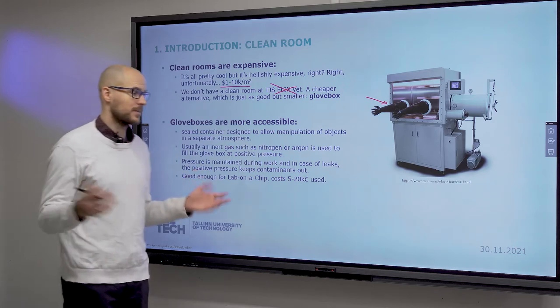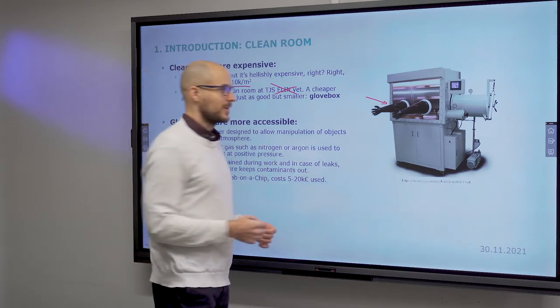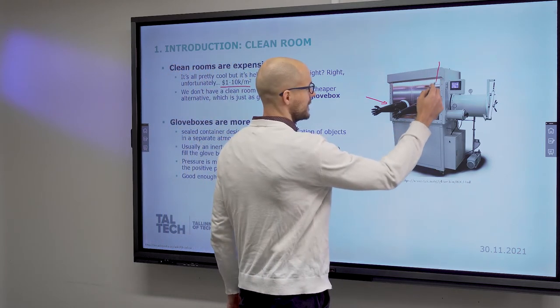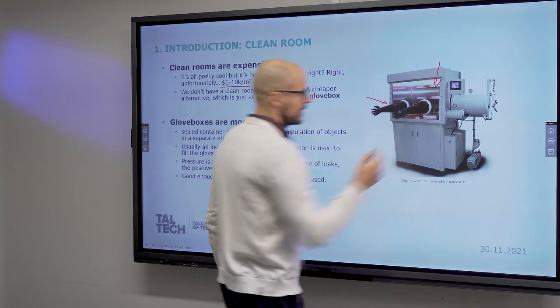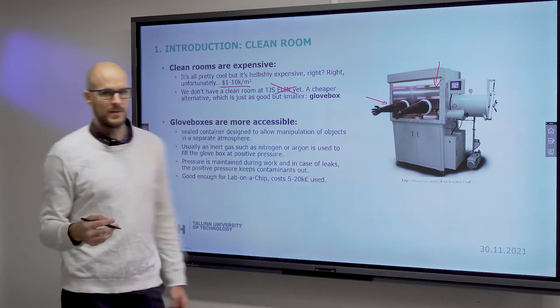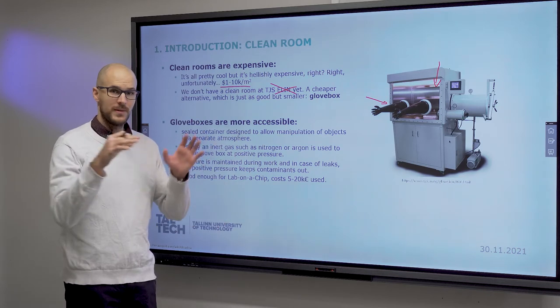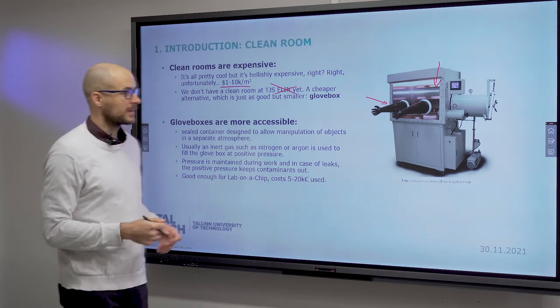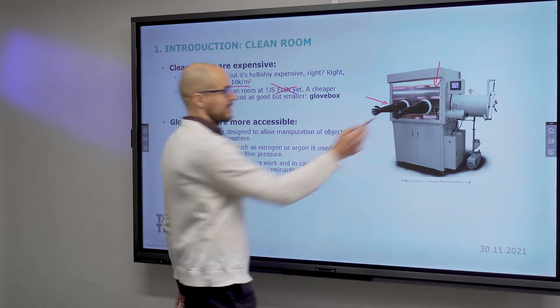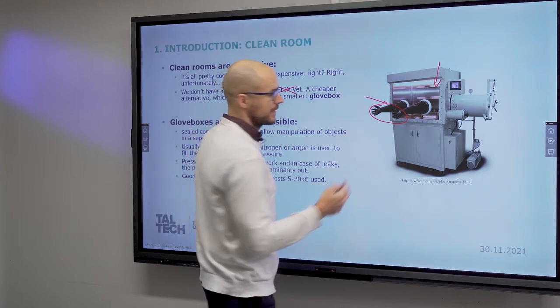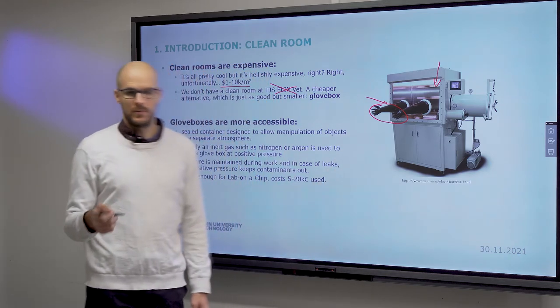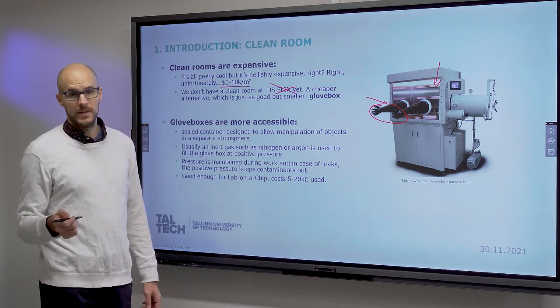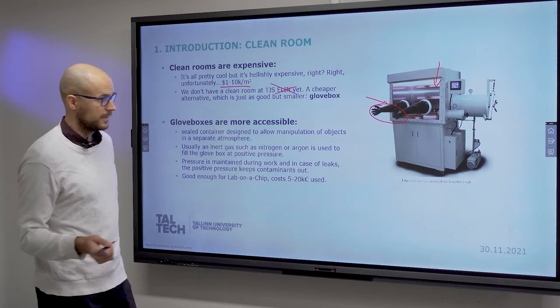So in a glove box, you have a positive pressure, which means the inside is kept at a high pressure. And that is to prevent dust from building up. So high pressure, if there's a leak anywhere, it goes out rather than being kept in. You can operate whatever is inside through gloves. And the pressure is maintained through a pressure regulator. It's usually with an inert gas, like nitrogen or argon.